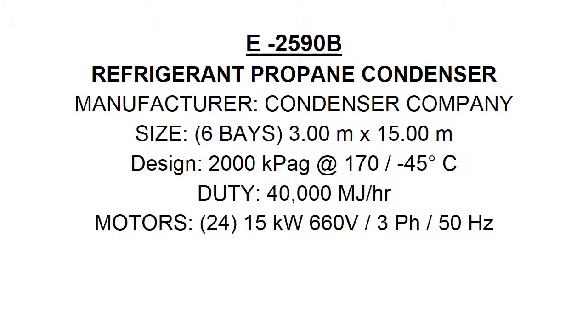Example label for a condenser: E-2590B, Refrigerant Propane Condenser. Manufacturer: Condenser Company. Size: 6 bays, 3 meter by 15 meter. Design: 2,000 kilo Pascal gauge at 170 / minus 45 degrees Celsius. Duty: 40,000 mega joules per hour. Motors: 24 x 15 kilowatt, 660 volt, 3 phase, 50 hertz.